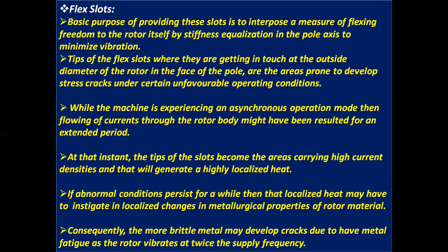Now let's explain the flex slots. The basic purpose of providing these slots is to interpose a measure of flexing freedom to the rotor itself by stiffness equalization in the pole axis to minimize vibration. Tips of the flex slots, where they are getting in touch at the outside diameter of the rotor in the face of the pole, are the areas prone to develop stress cracks under certain unfavorable operating conditions.